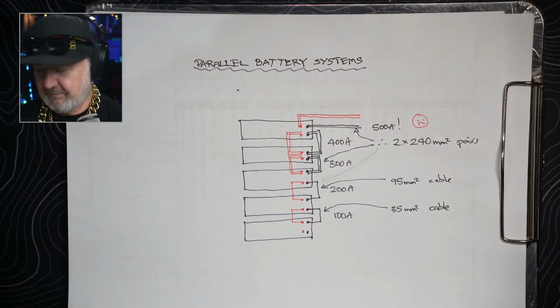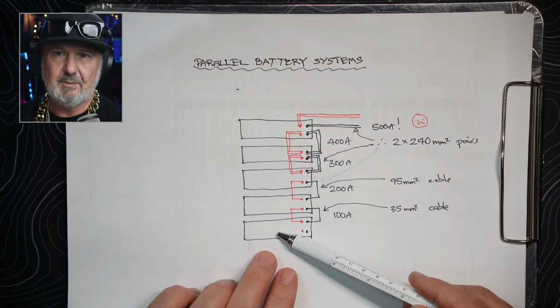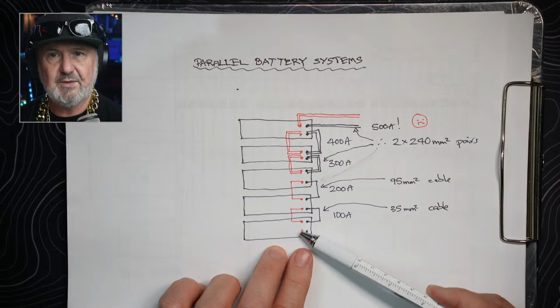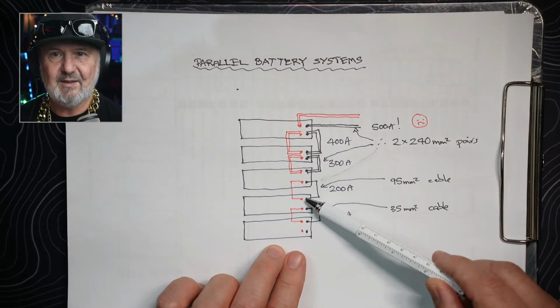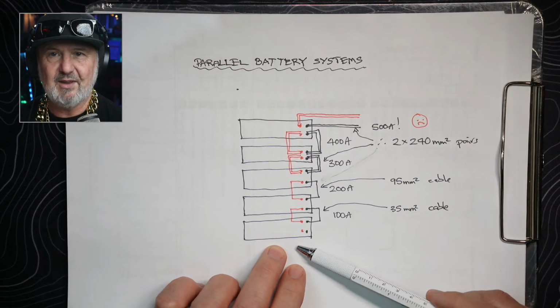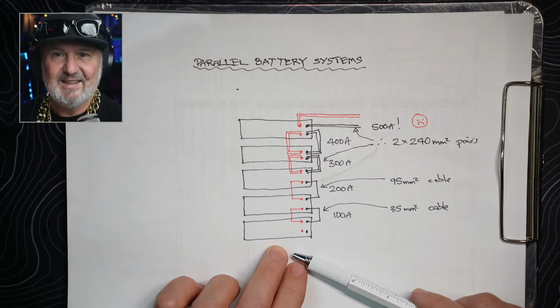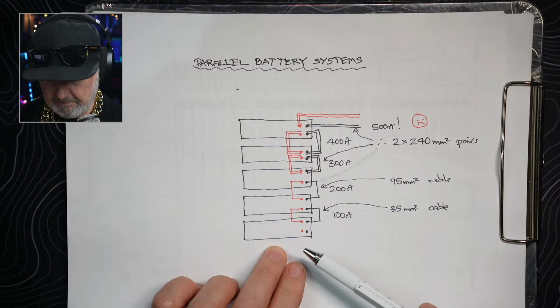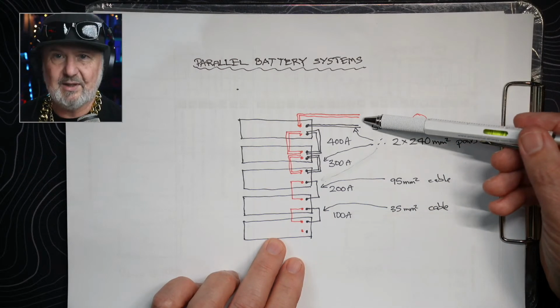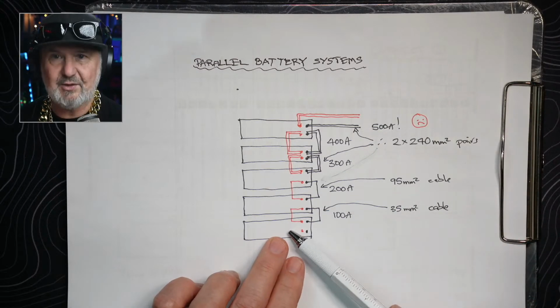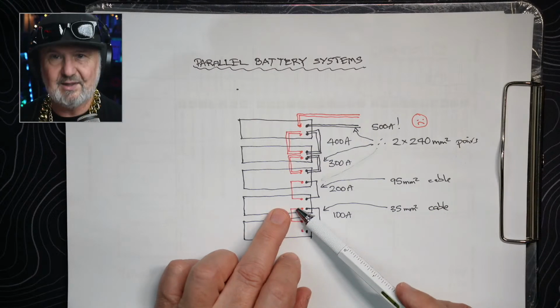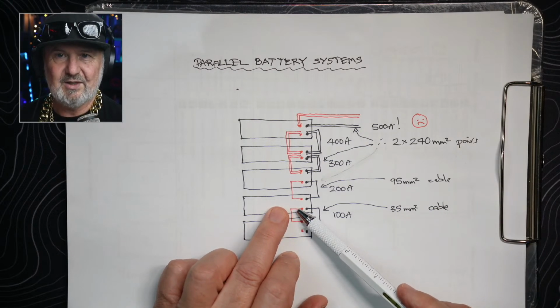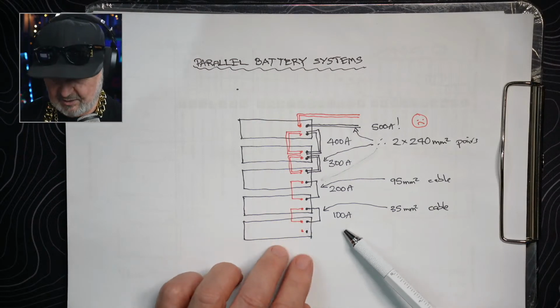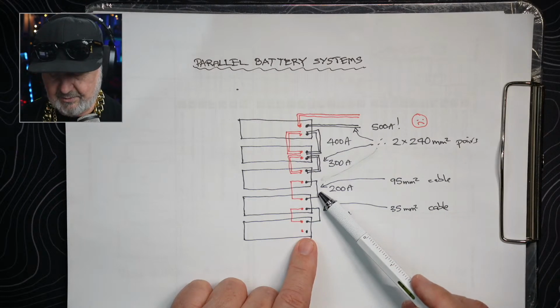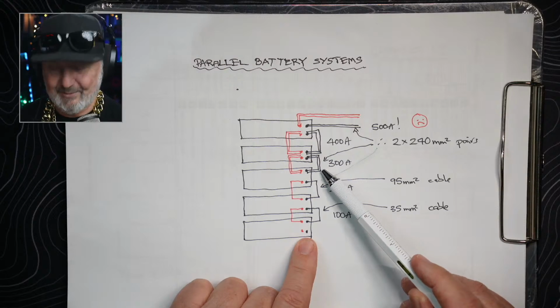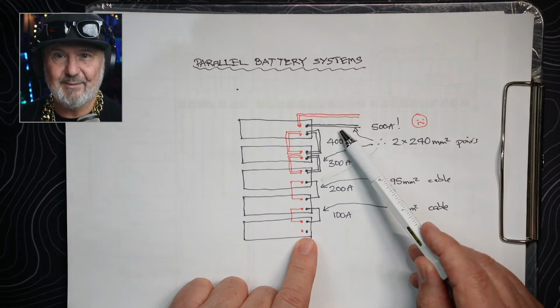Let's say these are 19-inch rack-mounted batteries, and they've got these double terminals, 2 positives and 2 negatives on each one, and they have little linking cables, so you can effectively parallel all of the battery modules together. When you think about it, the output is from the last one in the stack, and each of these battery modules can source 100 amps, but it's sourcing it in parallel to its output terminals. So we have 100 amps through this cable, 200 amps through that cable, under full power 300 amps through that cable, 400 amps through that cable, and 500 amps through that cable.